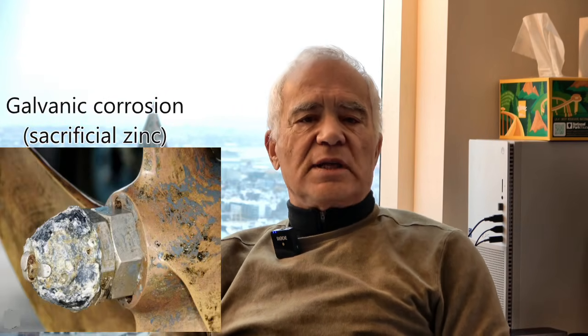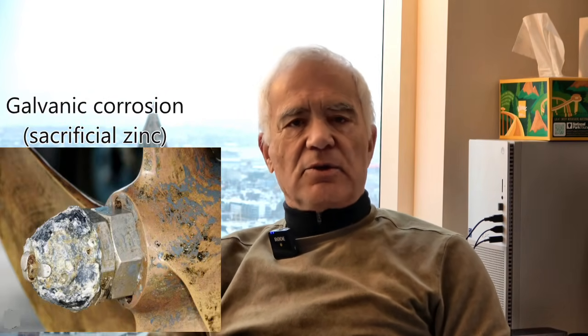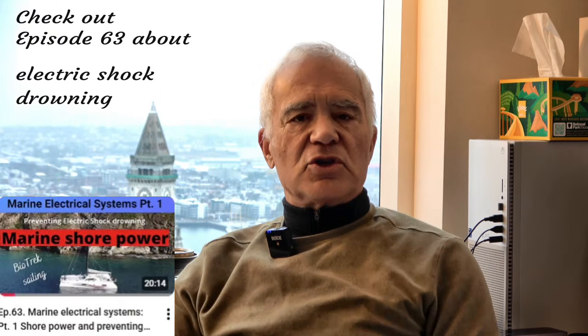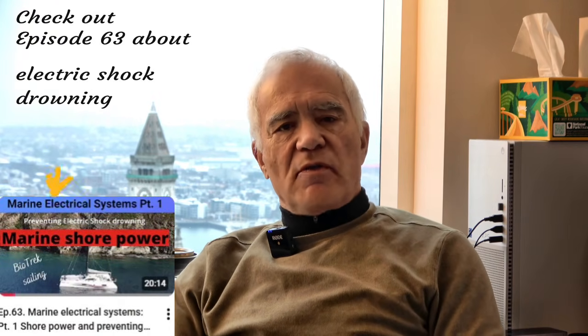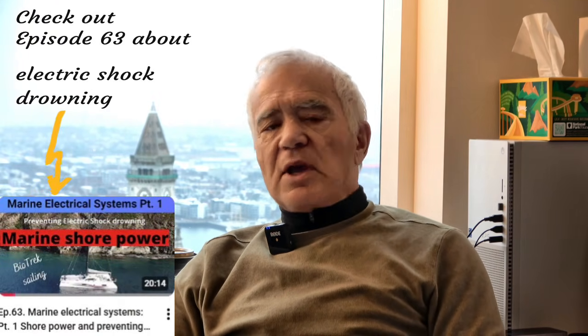The neutral leg will drift up and the high voltage will drift down. They both meet where the boat is, and we end up having large differences between the neutral and the ground, which creates galvanic issues, among others, the risk of electrocution if we're in fresh water, and a whole slew of other reasons. So, to make a long story short...